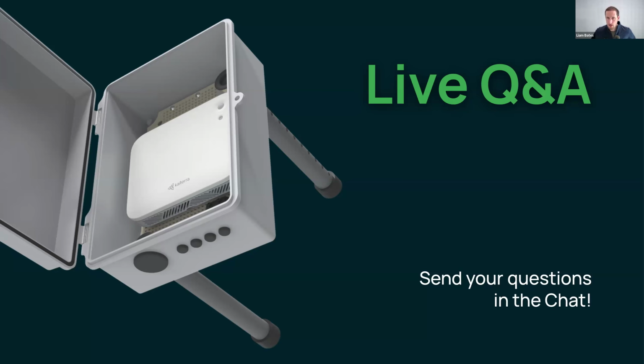We've got questions here around TVOC sensors—which chemicals are used to calibrate them, and what is it sensitive to? TVOC is a broad spectrum sensor, sensitive to a number of different VOCs that may be in the air, so it's not measuring a specific one. During the calibration process, isobutylene and ethanol are both used at different times.